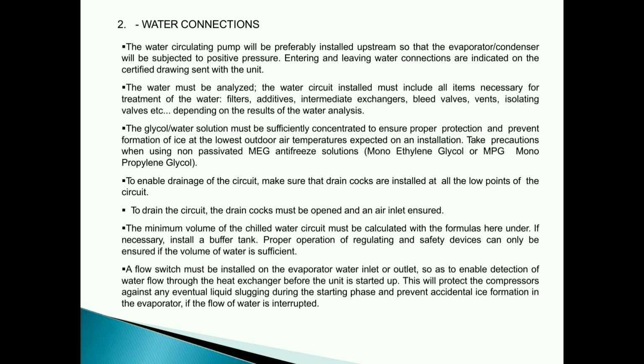The glycol water solution must be sufficiently concentrated to ensure proper protection and prevent formation of ice at the lowest outdoor air temperatures expected on an installation. Take precautions when using non-passivated MEG (monoethylene glycol) or MPG (monopropylene glycol) antifreeze solutions. To enable drainage of the circuit, make sure that drain cocks are installed at all the low points of the circuit. To drain the circuit, the drain cocks must be opened and an air inlet ensured.